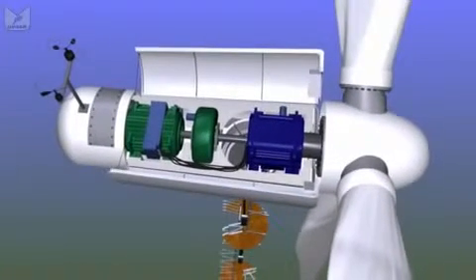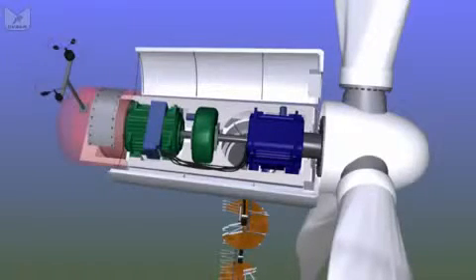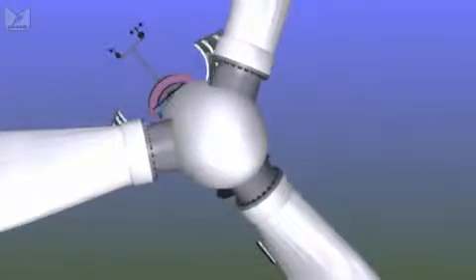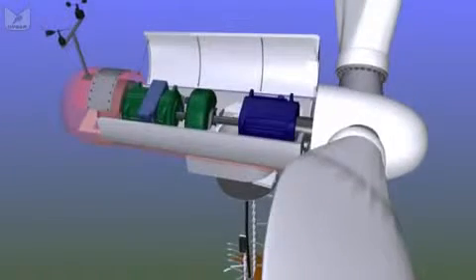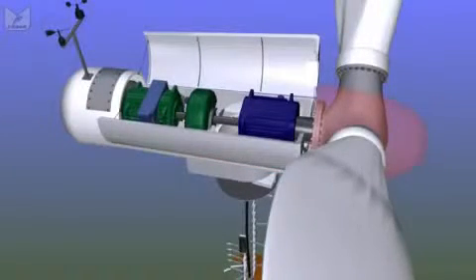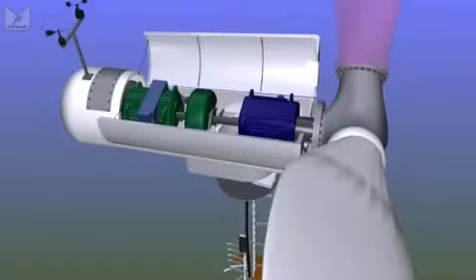And the nacelle in this case is a vaguely tapered tube. At the back we have the wind sensors, which give us speed and direction, and allow the turbine to face into the wind, and to change the angle of the blades. The nacelle itself is just a fibreglass tube. At the front we have a similar fibreglass cowl, protecting the hub, which is a steel casting, on which we have bolted our three blades.